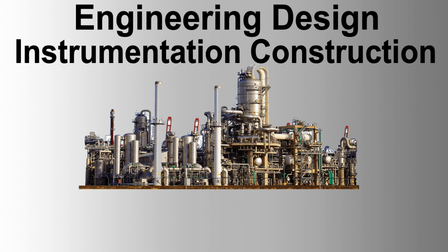Technical requirements. Temperature instruments. Wherever possible, thermowells shall be located downstream of orifice assemblies so as not to disturb the flow pattern in the line upstream of the orifice plate, or interfere with the requirements for unobstructed straight length. In vertical lines above rotating equipment, thermowells shall be located such that in the case of failure of the thermowell, it will not fall into the rotating equipment.